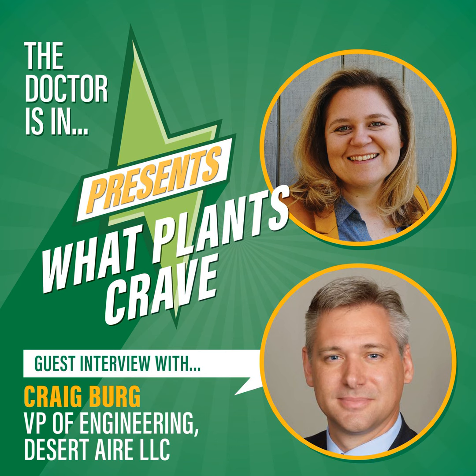Hot gas reheat uses the hot gas that was absorbed from the system. We talked about the great amount of energy absorbed during the dehumidification process, and the amount that goes in from the compressor to move that energy and bring the air's temperature down. With hot gas reheat, we take this cool gas that came out of the cooling coil and compress it, which increases its temperature, following the ideal gas laws, so now it's hot. We can use that hot gas for reheating the air, so that after the temperature drops off the evaporator coil, we flow it through a reheat coil, a hot gas reheat coil, using that compressor energy.